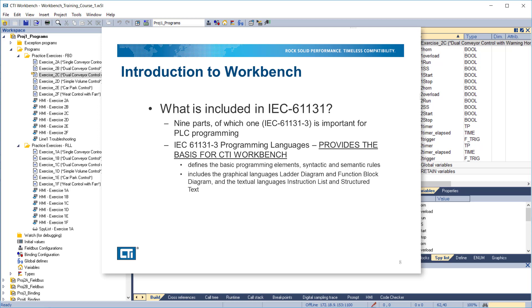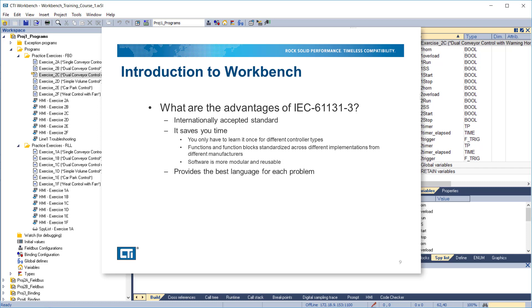IEC 61131-3 defines the basic programming elements, syntactic and semantic rules, and includes the graphical languages ladder diagram and function block diagram, and the textual languages instruction list and structured text. The advantages of IEC 61131-3 include being an internationally accepted standard, saving time since you only have to learn it once for different controller types, standardizing functions and function blocks across different implementations from different manufacturers, resulting software that is more modular and reusable, and providing the best language for each problem.